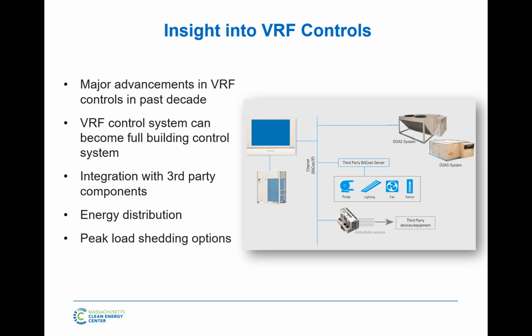Then I have to wire them back to my field controllers and give you some sort of graphic. With VRF, if somebody says, I got 100 units in this building with VRF, since I want to control those, all we have to do is take our condensing units, because our motherboards there are already wired to all the units, and daisy chain those to a central controller with the BACnet license on there. So that's option one. Big BAS, big building.